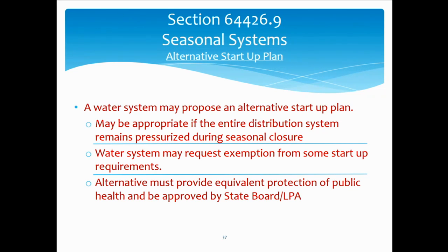No, they have to submit a startup plan, and once that plan is submitted and approved, then that's what they would do every year. So in your instance where you have a campground in the high country that doesn't normally chlorinate, the water's really clean, if they propose, we're going to flush the system and repressurize it and take bacteriological T samples, and if they're clean, then that'll be our procedure. And if that's approved, then that's just what you would do every year. But that system would have to notify the state or LPA, we've done our approved startup procedure and we want to serve the public now and get approval to do that.